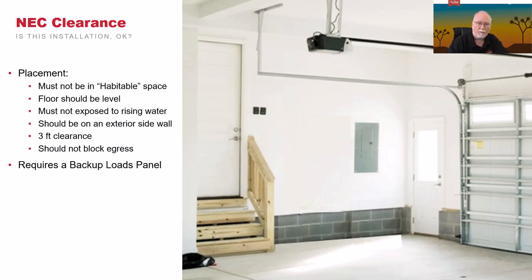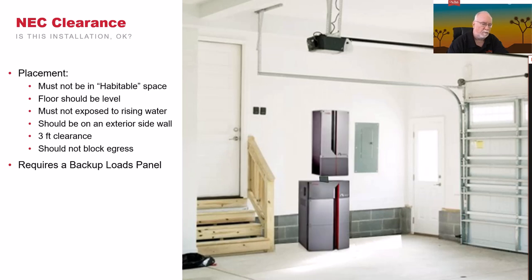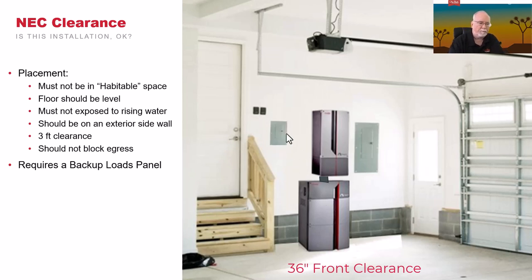So first step is we'll go ahead and drop the Mojave in place. We're going to hook it into the main panel, and then the next thing we're going to do is put in a backup loads panel. Now again, remember, there's a lot of things that fall into the NEC on this, so the backup loads panel actually can't be directly above the unit. You're going to have to slide it off to the side.